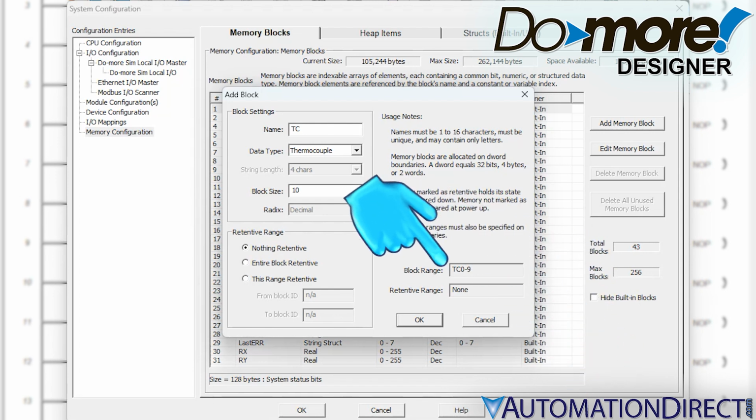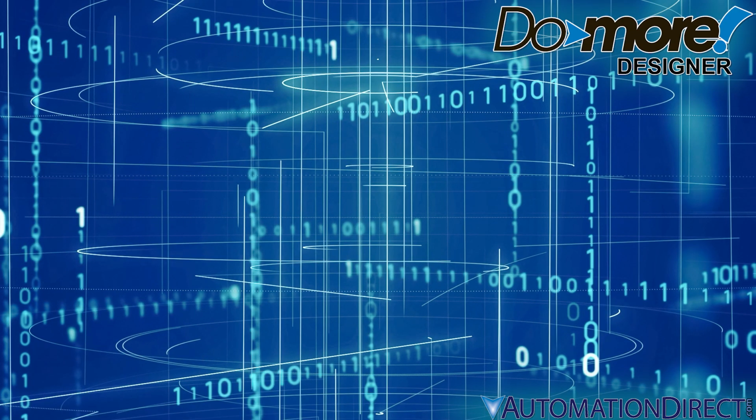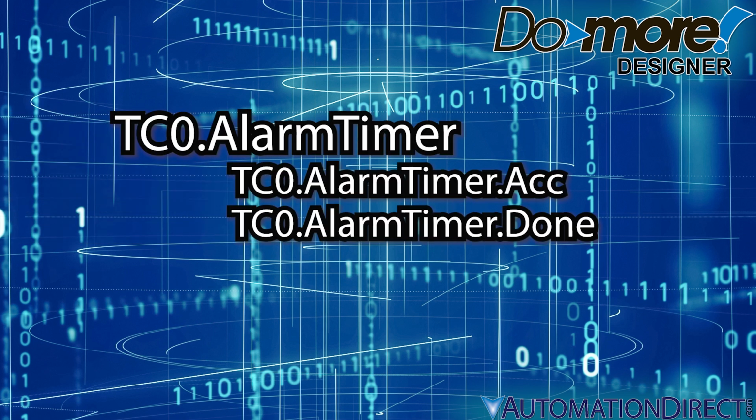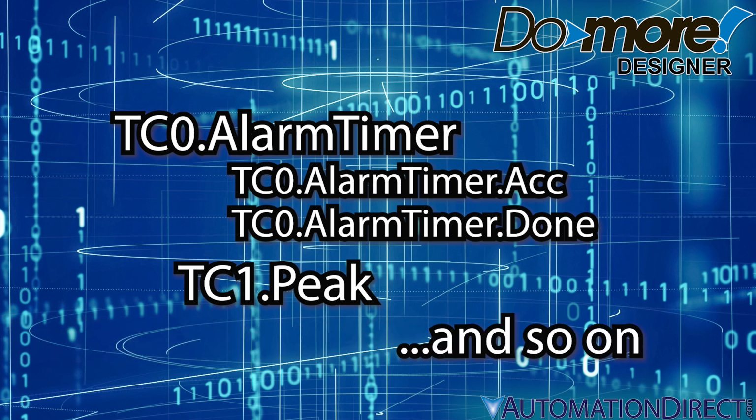Looking at the block range here, you can see that we are creating TC 0 through 9, and this is how you'll refer to these variables in your program. If we want to look at the alarm timer for our first thermocouple, for instance, we'll look at tc0.alarmTimer. tc1.peak will give us our second thermocouple's peak temperature, and so on.